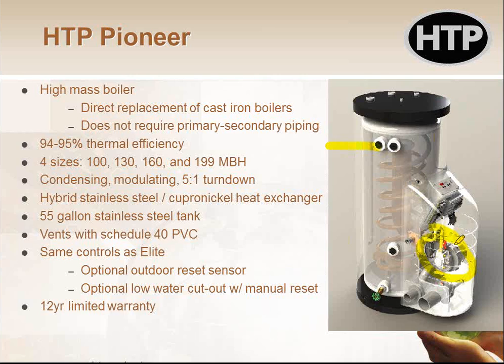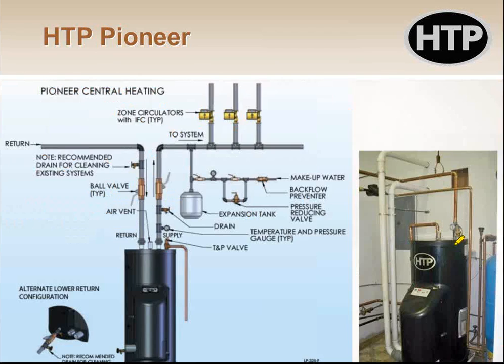And the low mass ones, because the water is moving through there so quickly, and the burner is so large relative to the mass of the water, we have to use that primary, secondary. Plus the pumping pressure drop kind of dictates we need two separate pumps. Whereas with the high mass ones, I can get away with just one piping loop. So as this example shows you here, instead of having two pumps on here and closely spaced tees right there, I don't have that. I just got water goes out the pump, comes back in. Now this one happens to have 3 zones, but most places just have 1 zone on these small boilers. But I don't have to have that primary, secondary piping in the middle there.